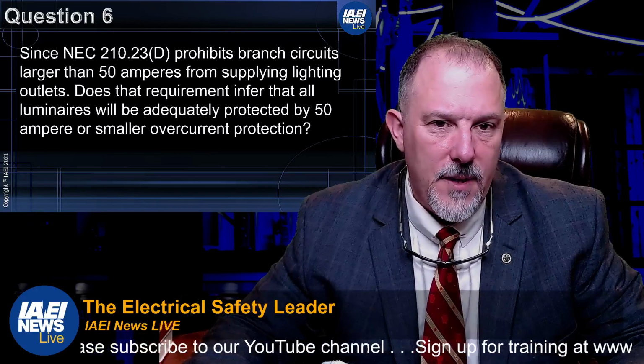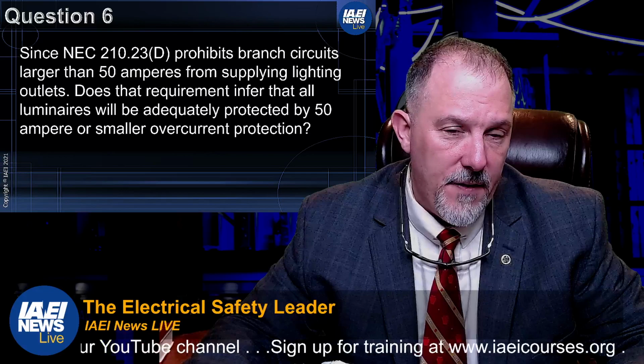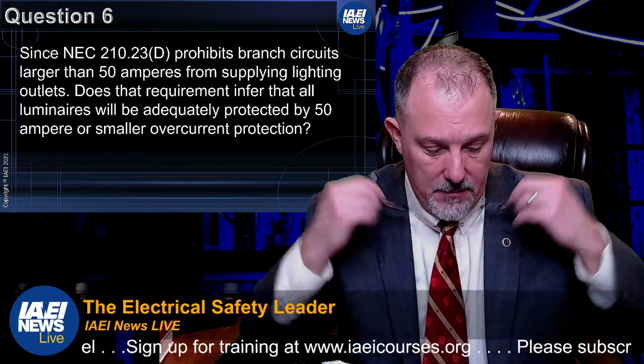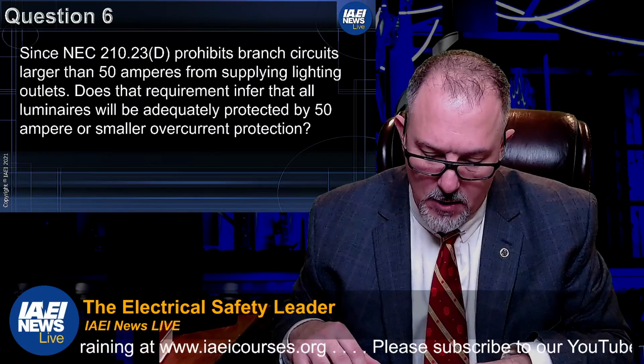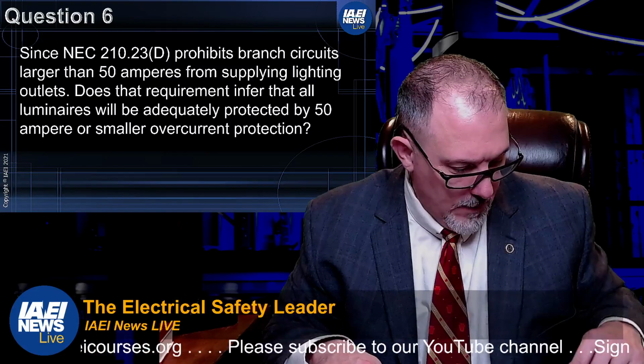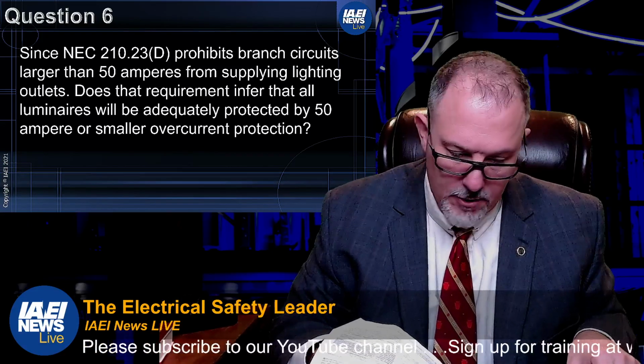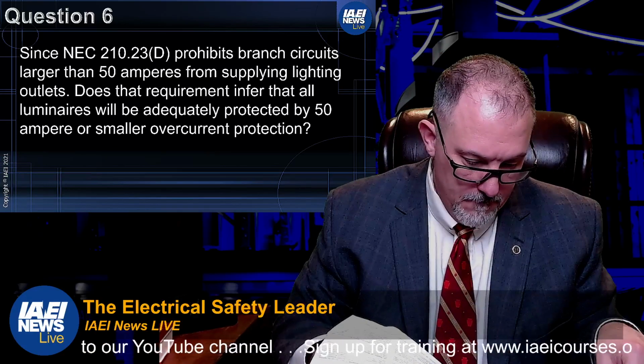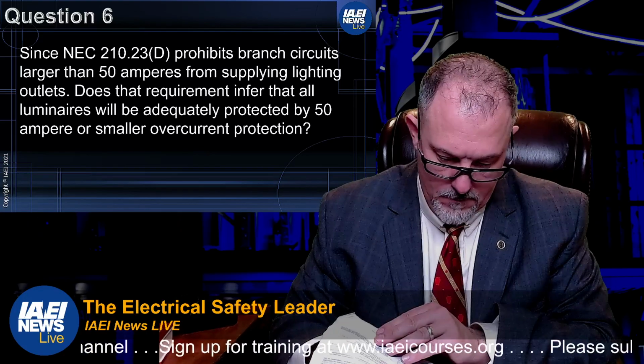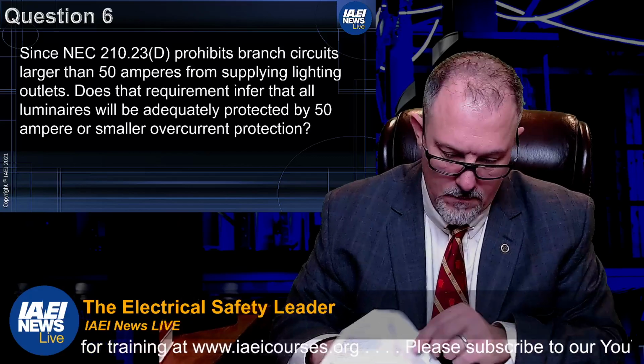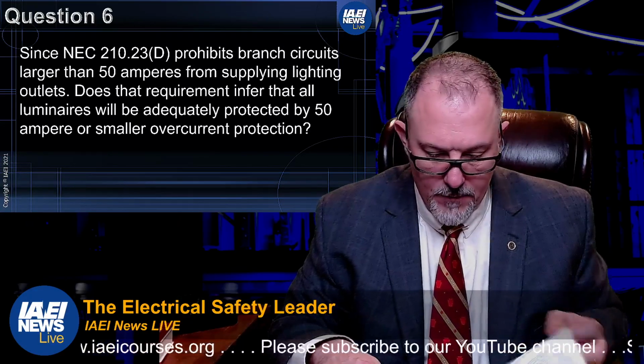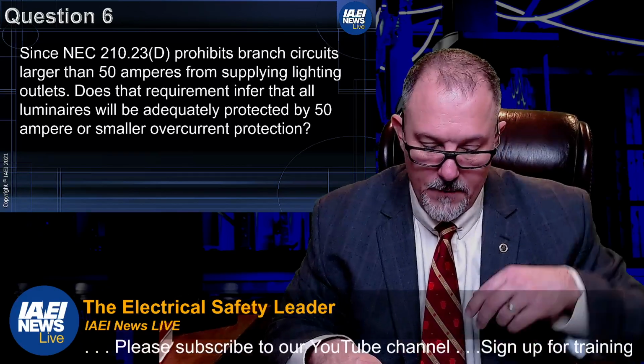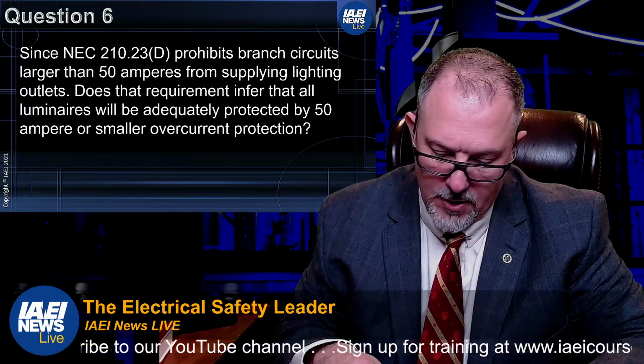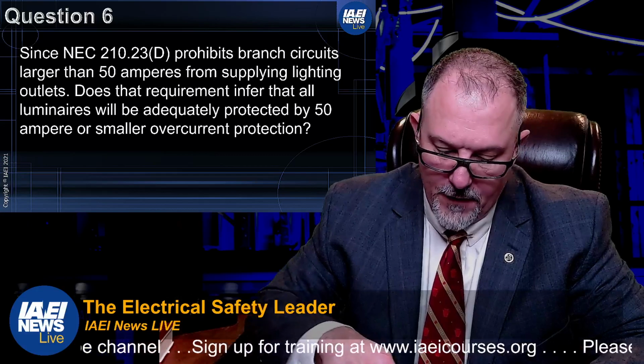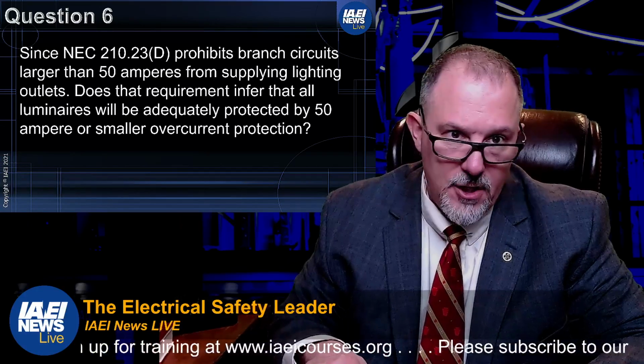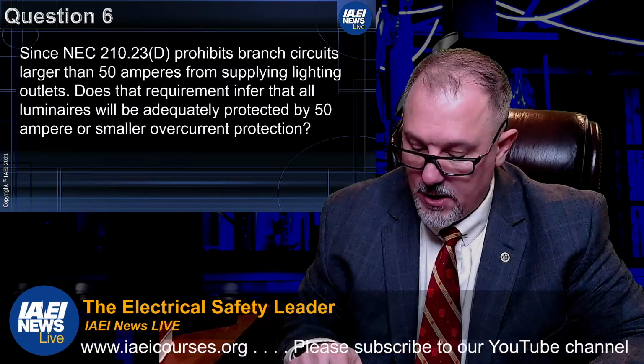Since NEC 210.23(D) prohibits branch circuits larger than 50 amperes from supplying lighting outlets, 210.23(D). 210.23 is permissible loads, multiple outlet branch circuits, right? And we are still in part 2. Part 1 is general. .23 looks like it is in part 2, branch circuit ratings. So 210.23 permissible loads, multiple outlet branch circuits. A is your 15-20 amp branch circuits. B is your 30 amp. C is your 40 and 50 amp. D, branch circuits larger than 50 amps.